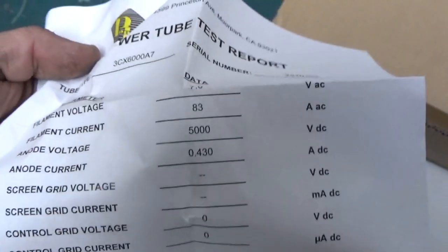So I'm going to do a hipot test on my Hipotronics. I've seen other people do it with some other type of transformer, current limited or whatever. But they're not. I believe they did it with AC. You're supposed to use DC and you're supposed to reverse the polarity between the elements. And short one element to the other. When you're, like this tube, you go between the plate and the filament. And you're supposed to short the filament. I'm sorry. Between the plate and the grid. And then have a short across the filament. Yeah, plate and grid. I'm sorry. I get up early. I'm tired. Okay, so when you're testing between the plate and the grid, then you want to put a short between the grid and the filament. And then when you go test between the grid and the filament, you want to have a short between the grid and the plate per Eimac specs, procedure or whatever. And then you want to be able to reverse the polarity. The idea is if there's a broken wire, you want to be able to pull it one way or the other. That's about it.